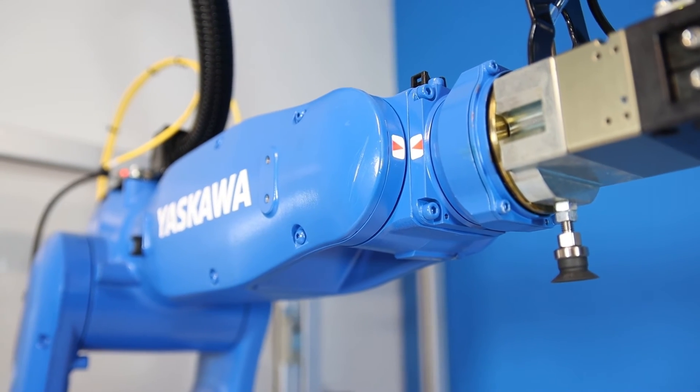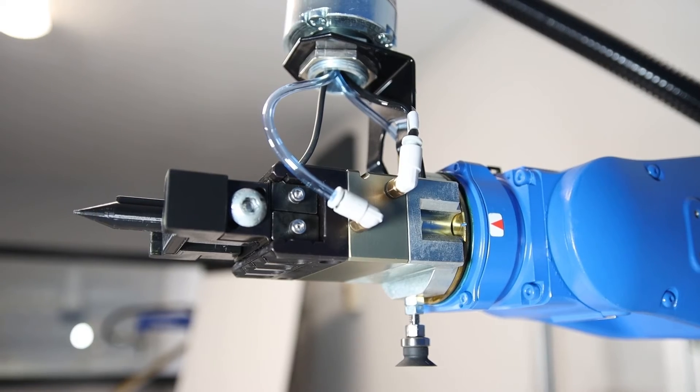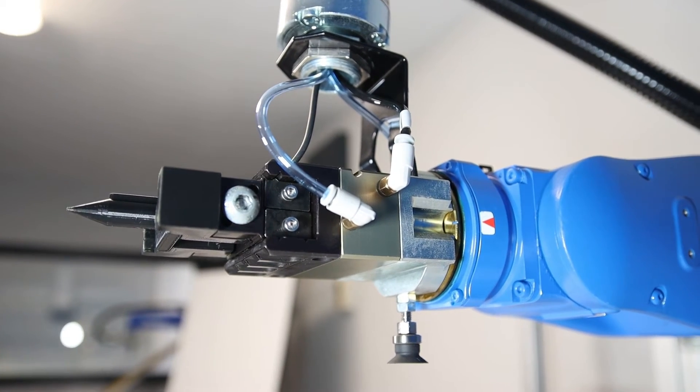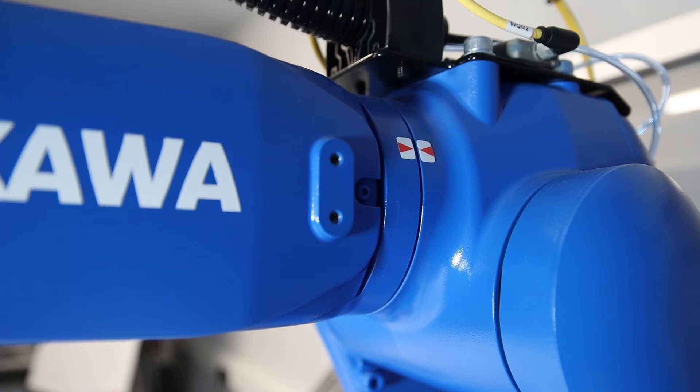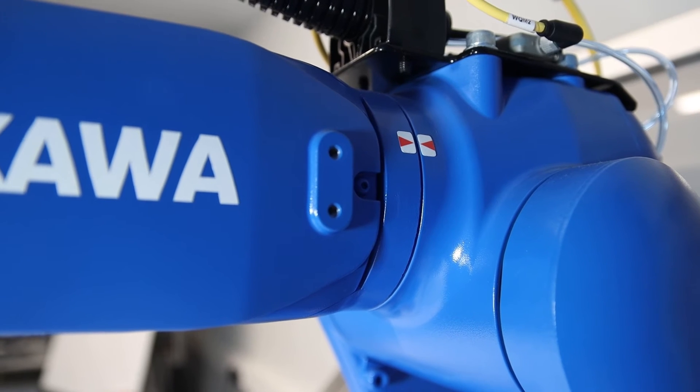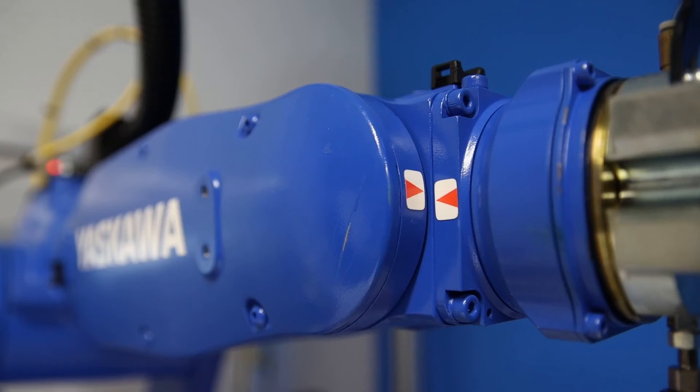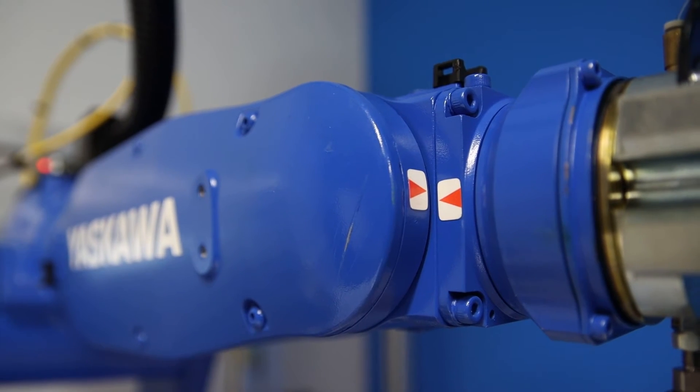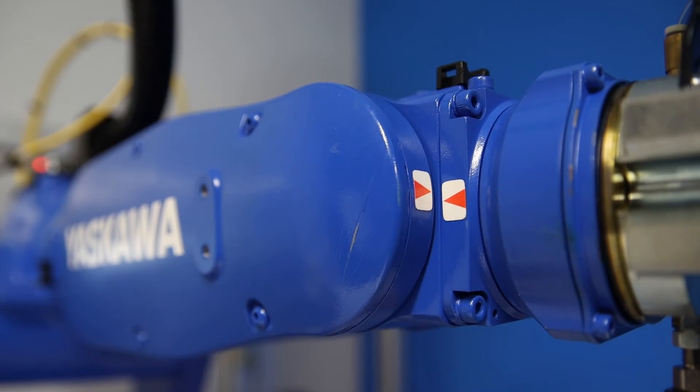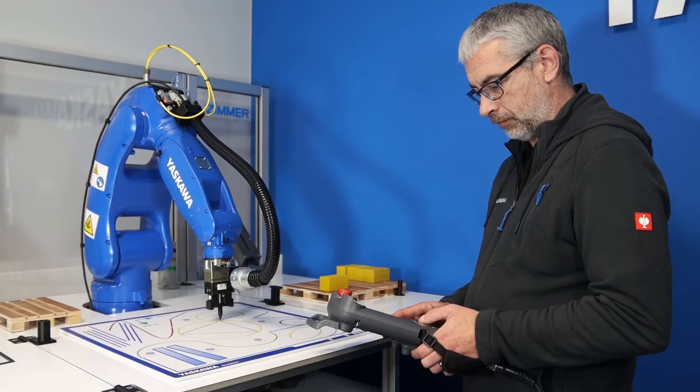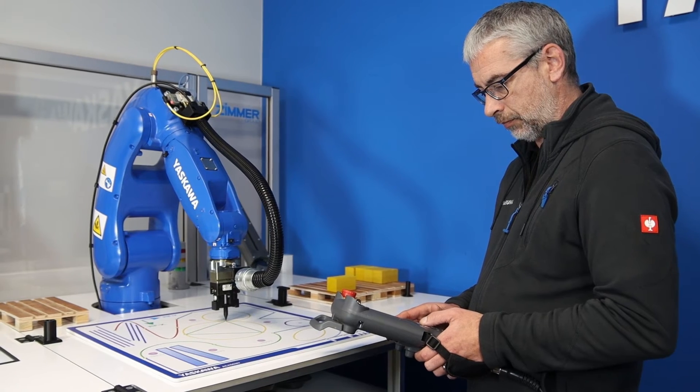Visually check the calibration marks for each axis to ensure no slippage has occurred. In the unlikely event that one or more axes have slipped, a recalibration of the axis will be required.